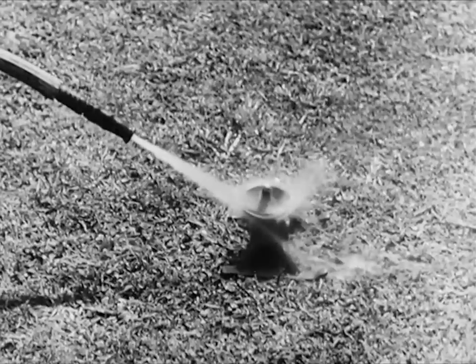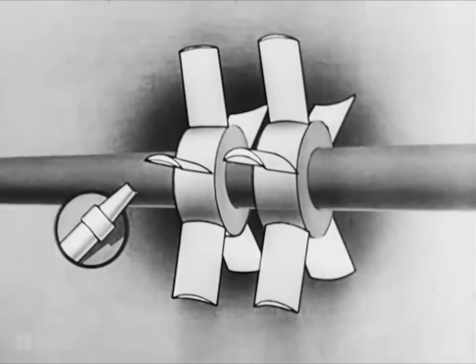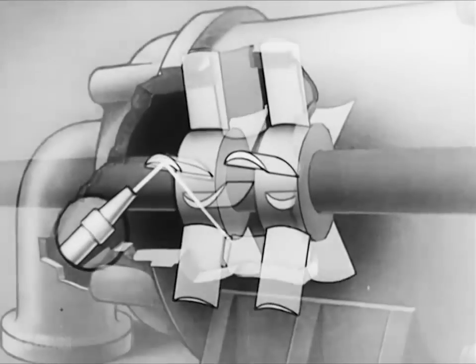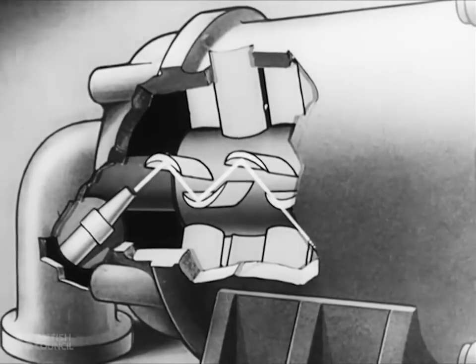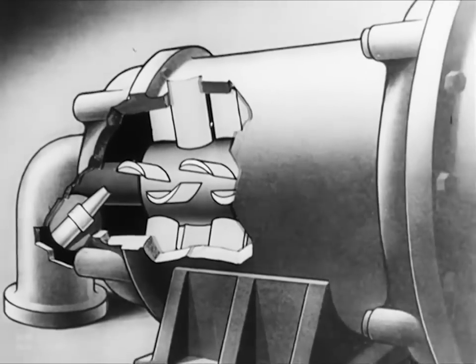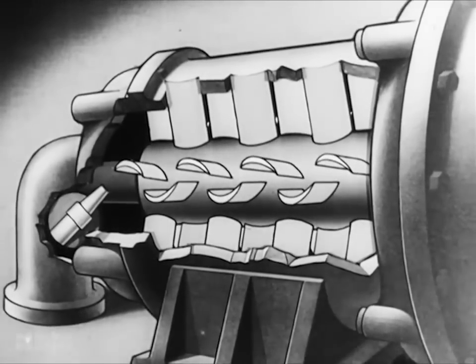The next stage is to redirect the steam so that it will be able to drive the second wheel. This is done by a set of fixed blades attached to the casing of the turbine, which are similar in cross section to the blades on the wheel, and deflect the steam again through 90 degrees so that it impinges on the blades of the second wheel at the same angle as on the first wheel. In the actual turbine, this arrangement is repeated through many rows of moving and fixed blades to ensure the best possible use of the energy of the steam is made. You can see how the Parsons turbine combines the ideas of Hero and Branca.